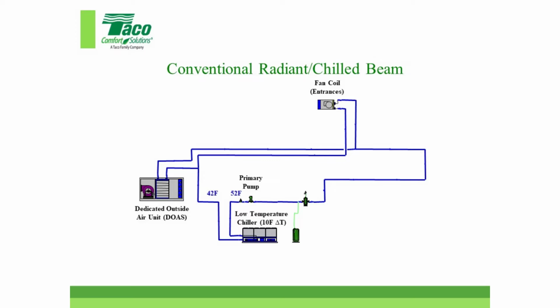You still need that in a chill beam system because you have to dehumidify the air coming into the building. Then you also need some type of distribution of warm cold water. What I mean by that is something above the dew point. I'm showing 58 degrees, it can be 55, it can be 60, it can be 52, but it's above the dew point. It's not 42, right? It's 58. So there's two piping systems all of a sudden.